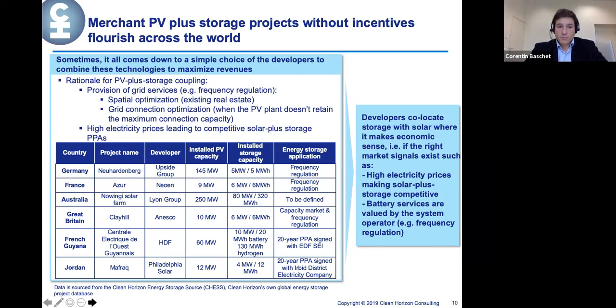What's the rationale behind it? First, if you're a developer and you have a PV power plant, you already have the connection, you already have the land, so it doesn't cost much more to add a storage component on the land. The footprint of storage is not much compared to PV, so you probably have enough room for storage, and the operation of storage doesn't need to be coupled with the PV operation. I'll touch on this for a second because it's important - you can have a PV plus storage plant where there is absolutely no interaction between the storage component and the PV component.